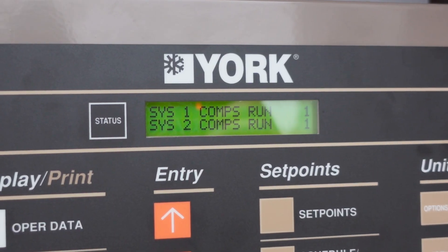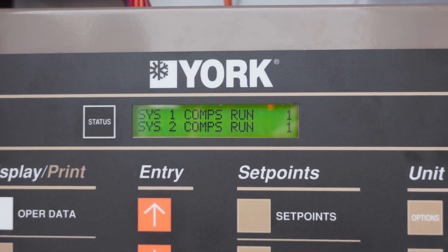Let's talk about different types of staging. Specifically, there are two main types I want to cover today: discharge air temperature staging, sometimes abbreviated DAT, and suction pressure staging — which is used on the comfort side and used to be a lot more common than it currently is.